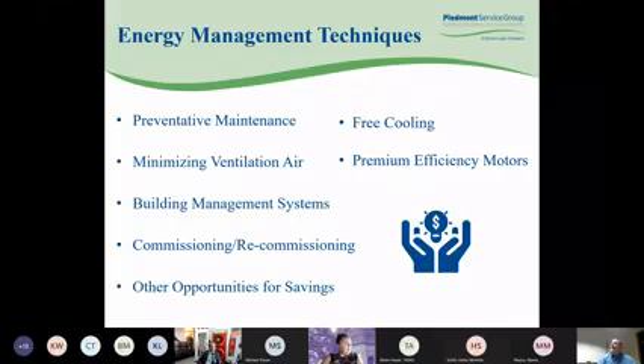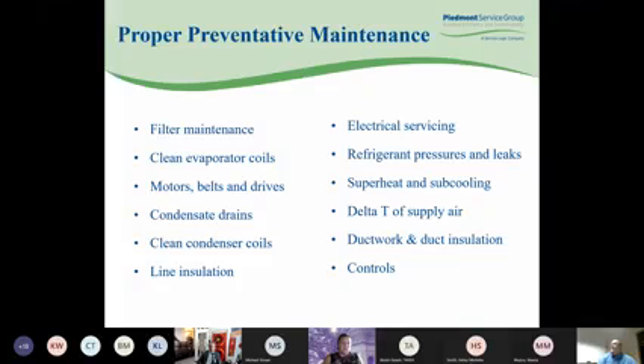So in the techniques, we should be looking at preventive maintenance, minimizing ventilation air, building management systems, commissioning and recommissioning, other opportunities for savings, free cooling, premium efficiency motors. Assuming that equipment is properly installed and is operational, it will not get more efficient after the commissioned startup. Maintaining the equipment is the best way of assuring its continued efficient operation. Scheduled maintenance should follow the manufacturer's recommendations.